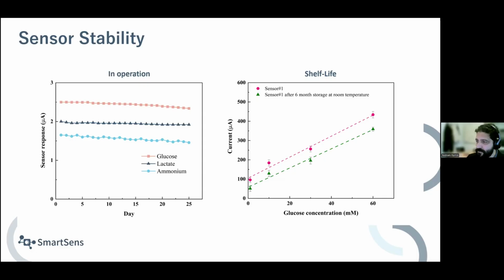About the stability of the sensor, this is the very big advantage of having bio-free sensors. In operation, we tested it. They can last for 25 days. Of course, the response drops. You can actually try it for longer if you want to. And the shelf life stability, we tested after 6 months. So basically, you can leave the sensor at room temperature in the lab environment, and then you come back and use it again. This is very important, for example, for single-use bioreactors, when you may need a long shelf life stability.